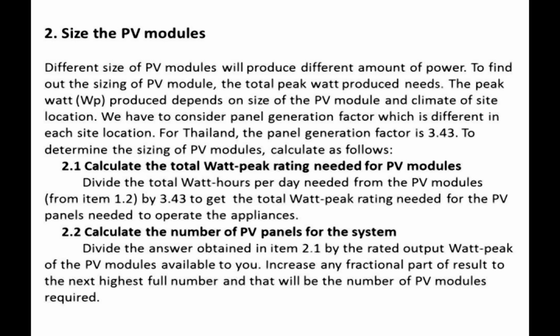Step 2: Size the PV modules. Different sizes of PV modules will produce different amounts of power. To find the sizing of PV modules, the total peak watts (Wp) produced must be determined. Peak watts depend on the size of the PV module and the climate of the site location. We must consider the panel generation factor, which is different for each site location. For Thailand, the panel generation factor is 3.43. Step 2.1: Calculate the total watt-peak rating needed for PV modules by dividing the total watt-hours per day needed from the PV modules (from Step 1.2) by 3.43 to get the total watt-peak rating needed.